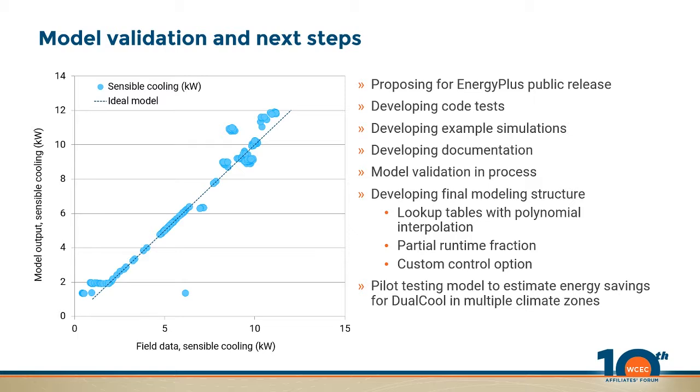It's true most of the modules point at polynomial curves, though there is a module within Energy Plus that allows you to define lookup tables, and you can take any of those air conditioner models that are looking for curves, and you can literally just change the name to a lookup table, and it'll look up the lookup table instead. And the utilities that they have for these lookup tables can do a few different things. They can take the lookup table and create a polynomial curve set, if that's appropriate, or it can sort of ignore the fact that the air conditioner model is looking for a polynomial in particular and just give it the value that it needs. And so that utility already existed within Energy Plus, though it has limited dimensionality, and we worked with NREL through this project to extend the number of independent dimensions to 6.